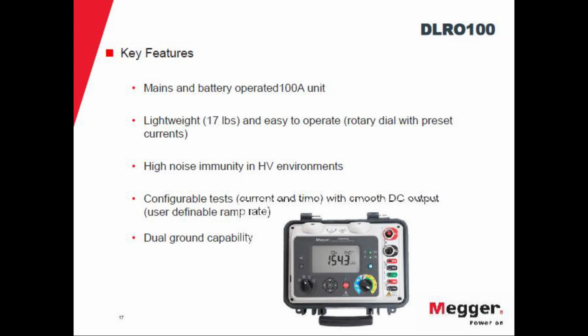But in any of these positions, you can use these arrows to change the current value. So you can be in the 100 amp setting, but you can change the current to 50 amps or to other values, in steps of 1 amp starting from 10. So here you have your current leads, and here you have your potential leads. So you can do the measurement as I was showing before.